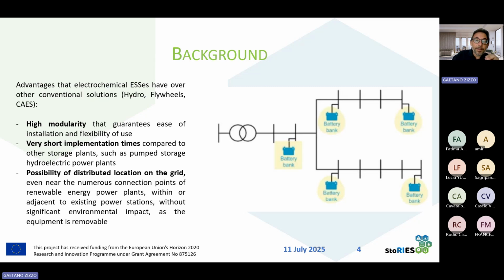Finally, we have the possibility of distributing various electrochemical electric storage systems in various locations of the grid. So we don't need a unique hydro pump storage in one place. We can install different units at various points of the grid, and in this way we can provide different services to the electrical system. We can install the right system for the existing infrastructure, without modifying the section of the lines, for example, or the rating of the transformers present in a given section of the grid, because we can choose the right solution for that node.